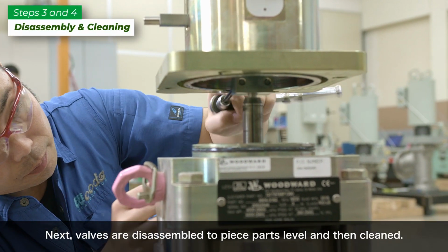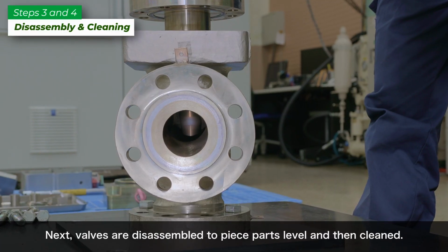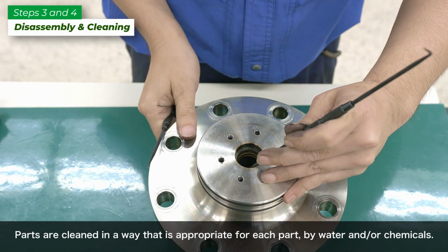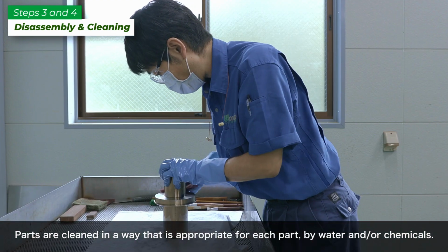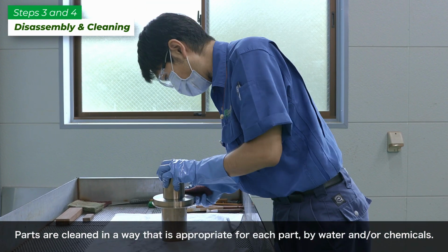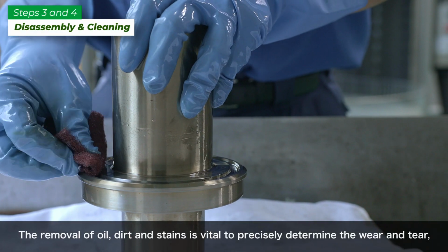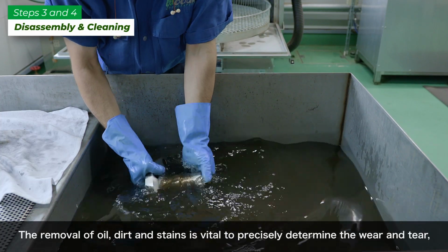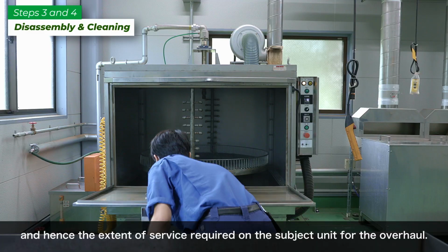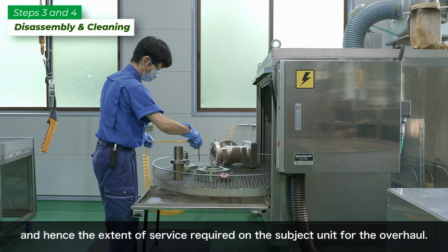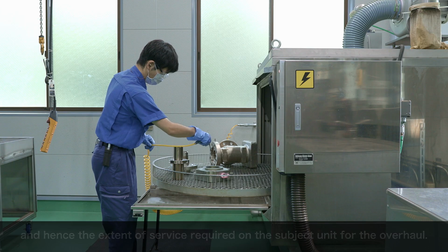Next, valves are disassembled to piece parts level and then cleaned. Parts are cleaned in a way appropriate for each part, using water and/or chemicals. The removal of oil, dirt, and stains is vital to precisely determine the wear and tear, and hence the extent of service required on the subject unit for the overhaul.